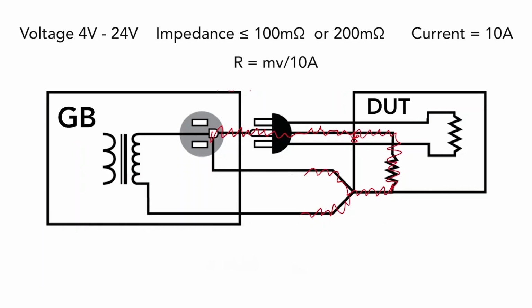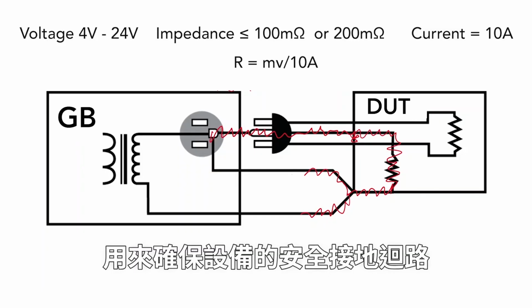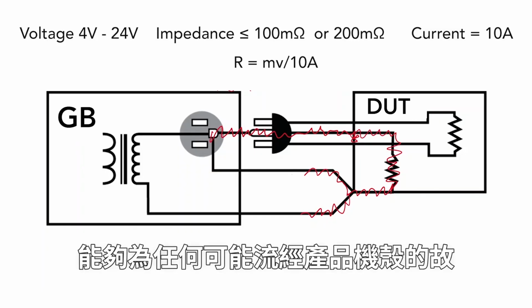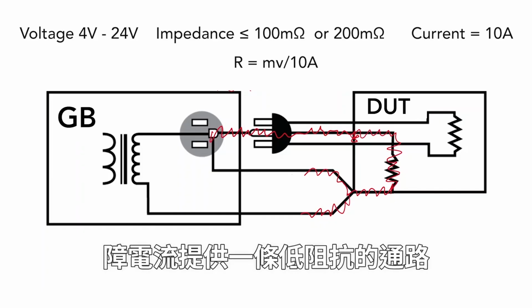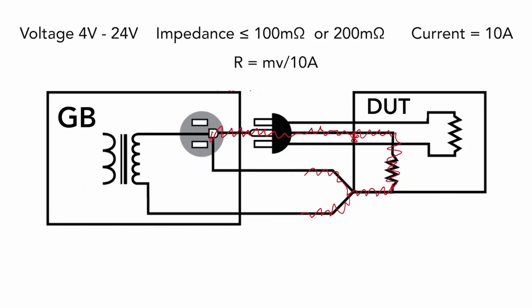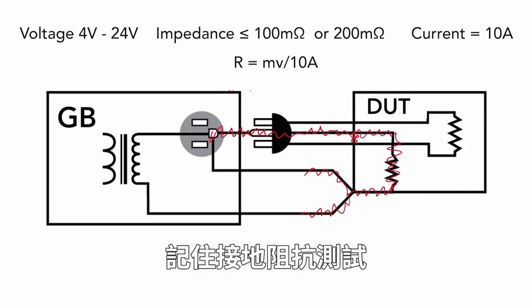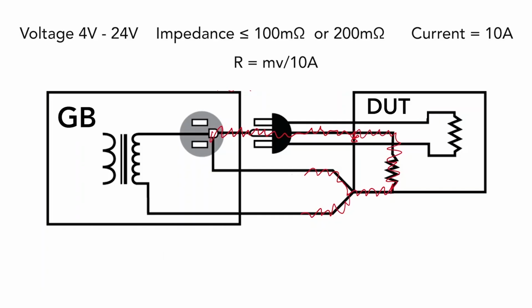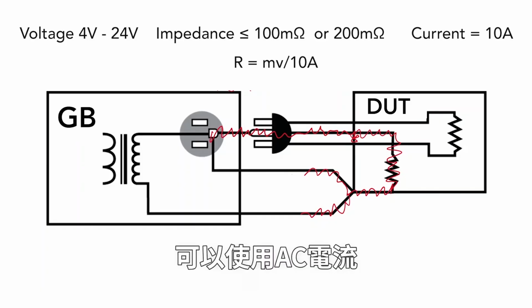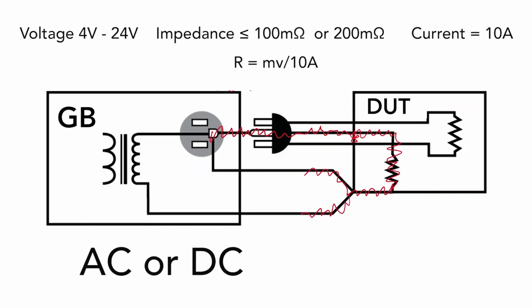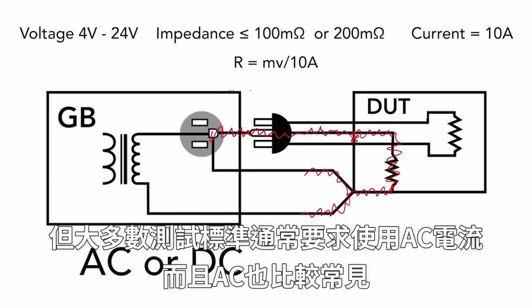Now, obviously, the ground bond test is used to make sure that the safety ground circuit of a device provides a low impedance path for any fault currents that may flow on the chassis of the product. Also, it's good to remember that the ground bond test is allowed using either an AC current or a DC current, but AC is more commonly required by most test standards.